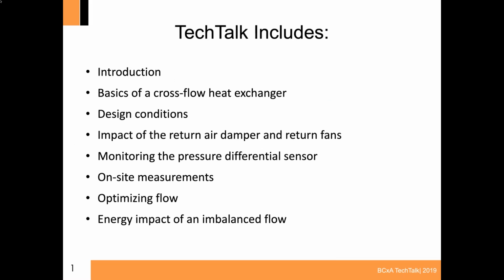What I'll do today is give a brief introduction and the basics of a cross-flow heat exchanger, for those that may not be familiar with them. I'll cover the design conditions they were designed to for temperature and airflow, the impact of the return air dampers as well as the return fans on energy recovery, monitoring the pressure differential across the cores, on-site measurements that were made, optimizing the flows across them, and what the energy impact of an imbalanced flow was across the heat exchanger.